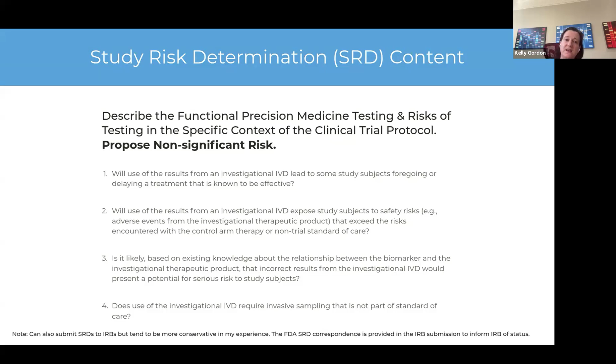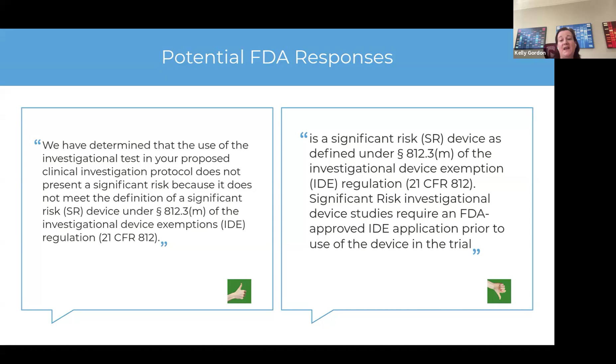These are the two answers that we get. This is the boilerplate language. On the left, this is what we want: we want them to tell us they don't consider it a significant risk, that it's a non-significant risk device. On the right is where they do consider it a significant risk and require an IDE. So at least you get an answer early on about what's required for the assay. And now I'm going to go into what an IDE looks like. A lot of people are scared about investigational device exemptions, but if you do a good job on the IDE and you're clear with your assay, they're easier to get through FDA.